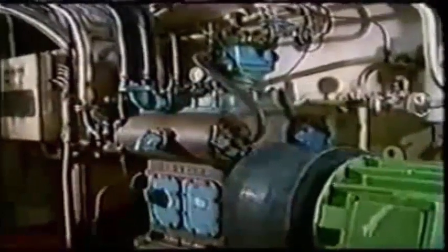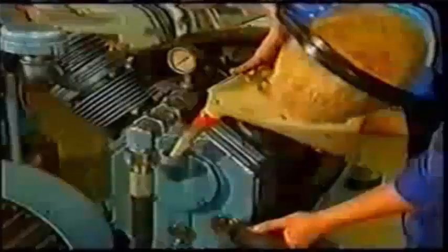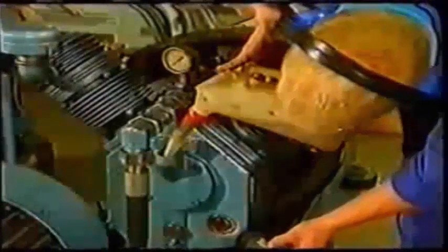When high tooth loading is combined with very high temperatures, then standard EP oils may not be sufficient. For such cases, it may be necessary to use synthetic-based oils, and a typical requirement arises for the lubrication of certain purifier gearboxes. Special compressor oils have been developed for use in certain designs of air compressors. These oils have to lubricate compressor pistons or vanes where high temperature and high pressure exists, and where air humidity can condense into water droplets.